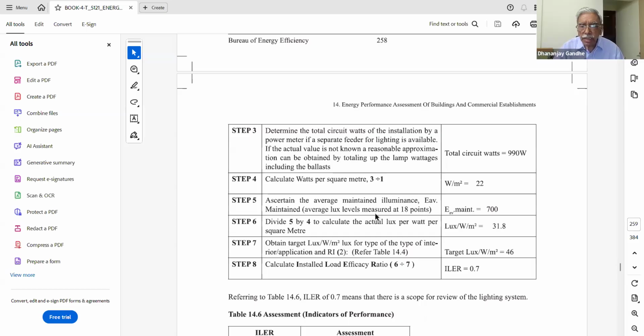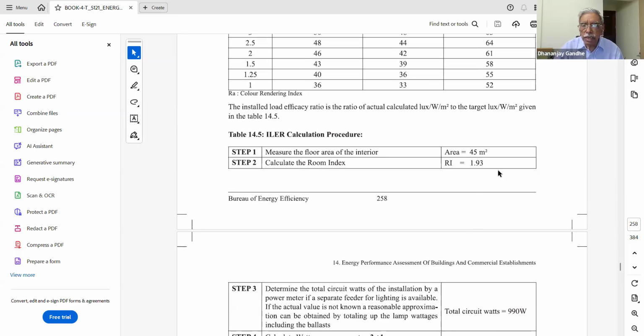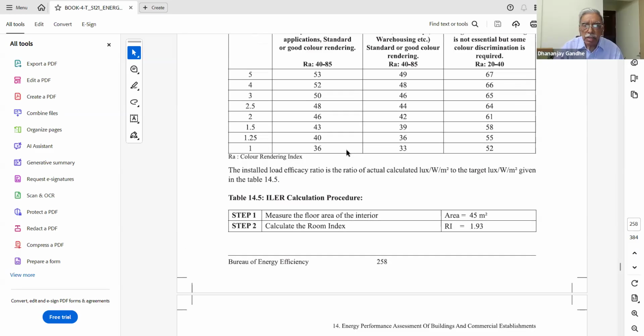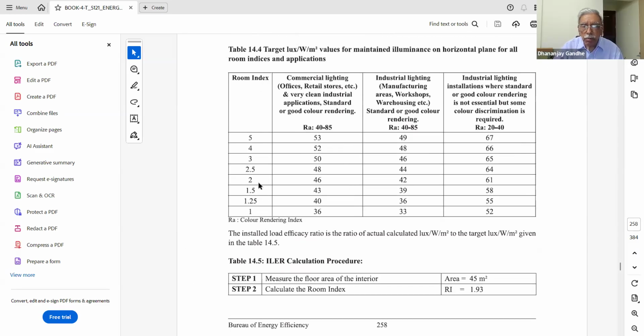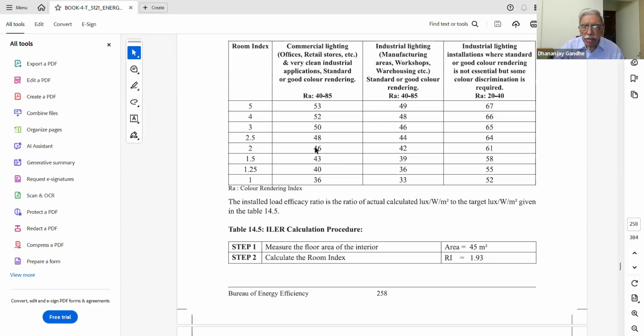The next step is you calculate the average illuminance at that particular place, that is measured. This measurement is at 18 points. Why 18 points? Because here the room index is mentioned as 1.93. So you refer to this table for 1.93, where 2 is the nearest level, and it is commercial lighting. So this target level should be 46. That is what is specified.